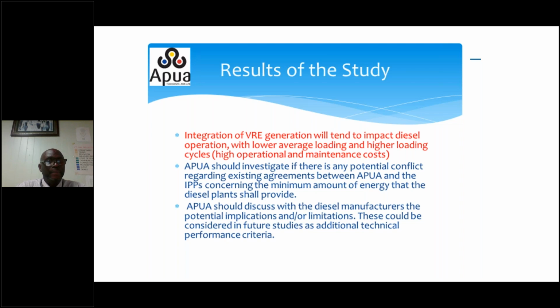The results of the study indicated that the integration of VRE generation will tend to impact diesel operation. Now, this is very crucial because VRE, as the name implies, varies: the sun shines and then there's a cloud cover. It means that the output from the VRE source varies. Now, in any power system, you have to maintain a certain frequency. In Antigua, it's 60 hertz. So it means if you lose generation from the VRE, you have to have generation from the fossil fuel plant. Or if that is not immediately available, then you have to have load shedding.